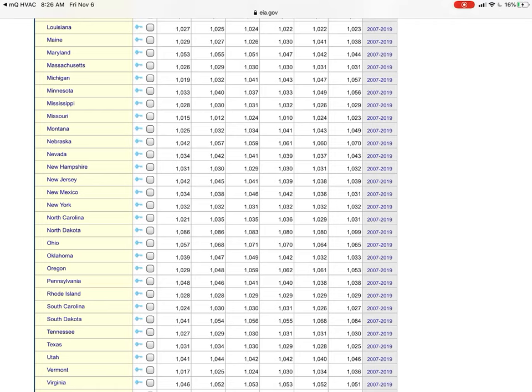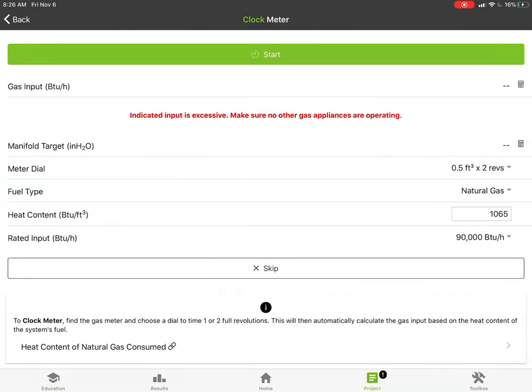You're going to enter in your heat content of gas, and then MeasureQuick will hold that going forward. But this is an average heat content over the year for the natural gas on there. So it is a starting point for you. You can call your utility and get it, but it's average heat content, not daily heat content, the gas we're concerned with.